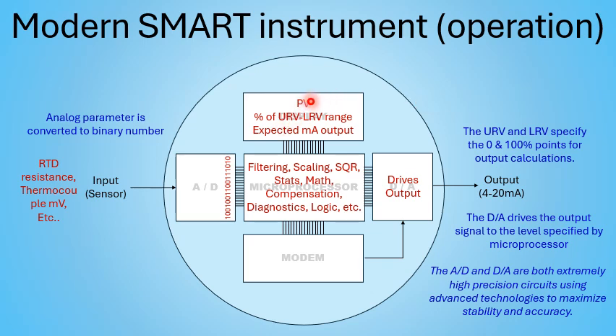You basically typically see the PV, the process variable, which is your input. That's what it's seeing from the analog to digital. It'll indicate the percent of the URV to LRV range. So it says 50%, you're halfway. And it'll tell you the expected milliamp output typically.